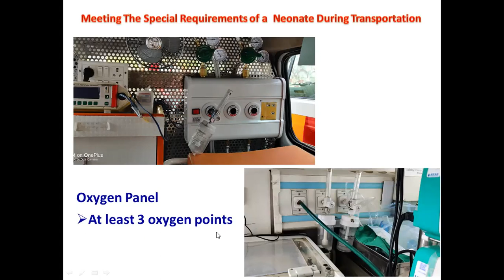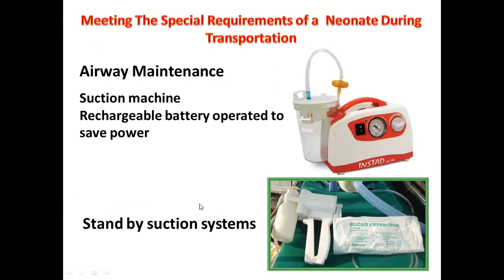Airway maintenance, suction machine is very important. And it should be rechargeable battery operated to save the power. You can't use the power of the inverter or the power of the ambulance to do suctioning. And there should always be a standby suction system. Transport ventilators ideally should be capable of delivering a minimum tidal volume of 2 ml. However, easier said than done. What is most popular is a gas powered ventilator because they do not require any power to run.